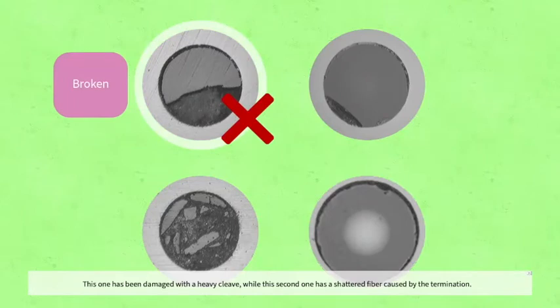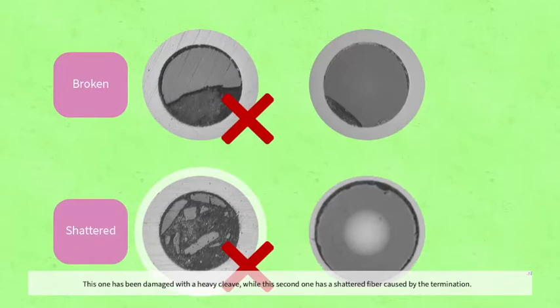This one has been damaged with a heavy cleave, while this second one has a shattered fiber caused by the termination. The fiber is broken inside the ferrule, and this connector should be discarded and is not repairable.